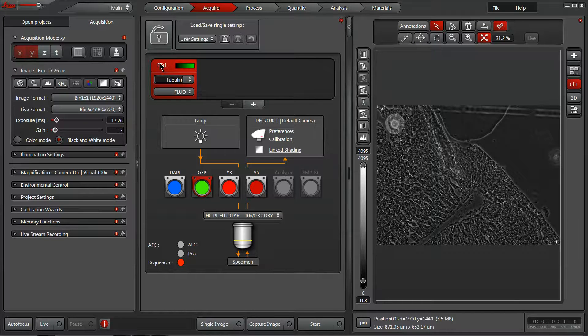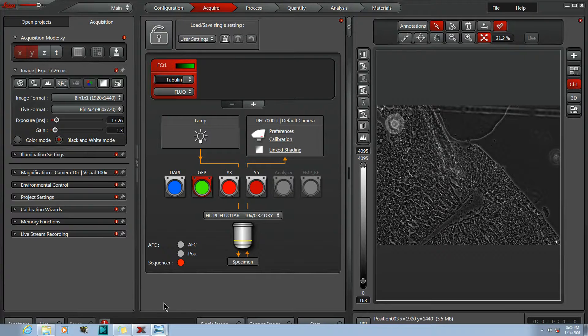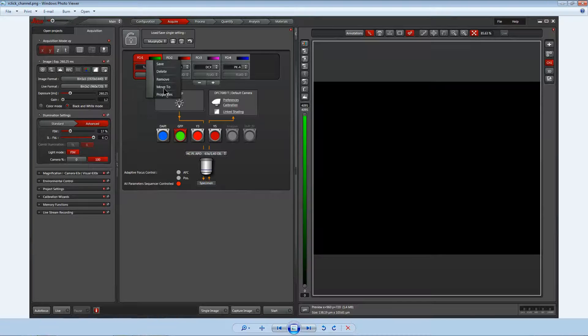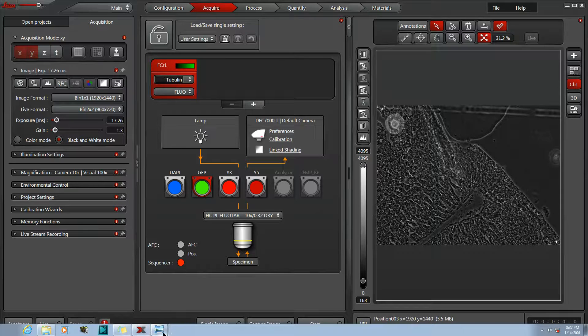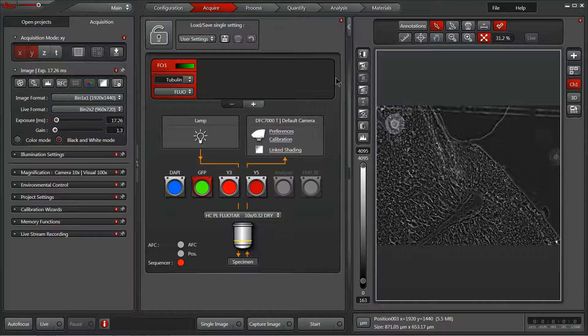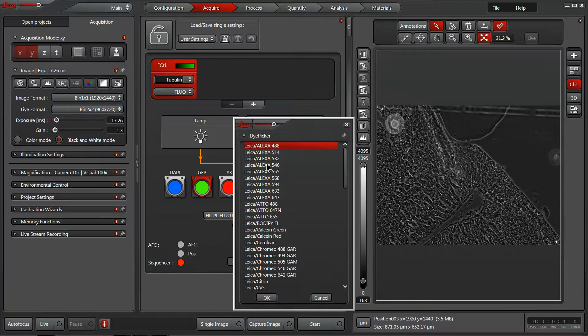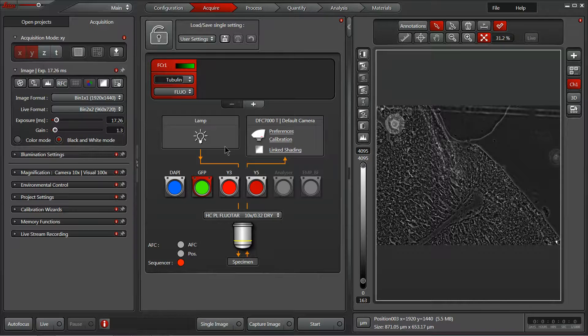Equally, if you right-click within a channel, you can get a menu. If you right-click on the channel and go down to Properties, you can actually pull up a list of dyes, which is a really useful way to tell the computer exactly what you're doing. With the dye list, you can select exactly what your probe is, and this will carry information with it. For example, with deconvolution we need our emission wavelength — by assigning the correct dye, we won't have to program that in later; it'll already know. I'm going to quickly do that and hit OK.